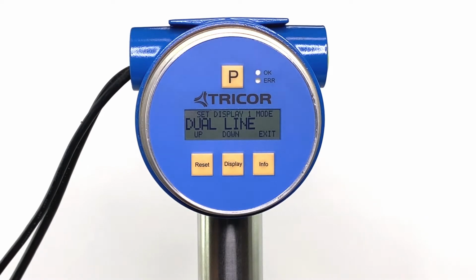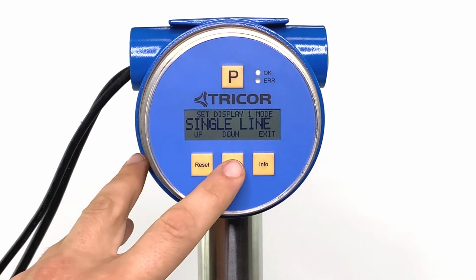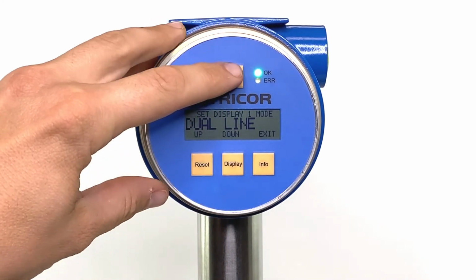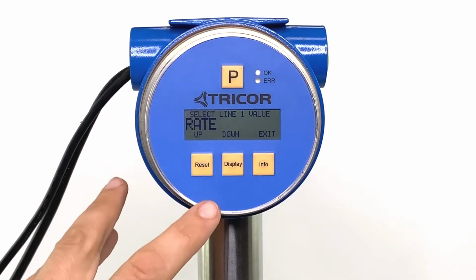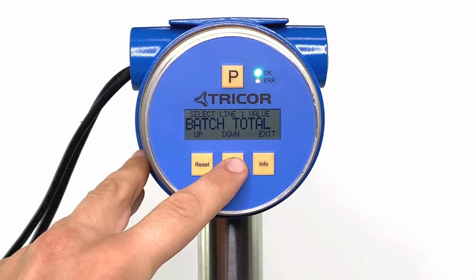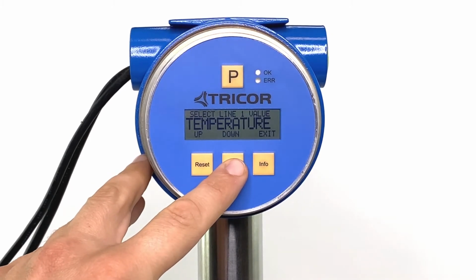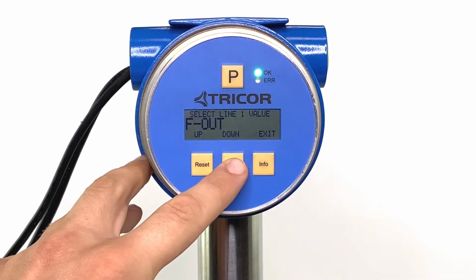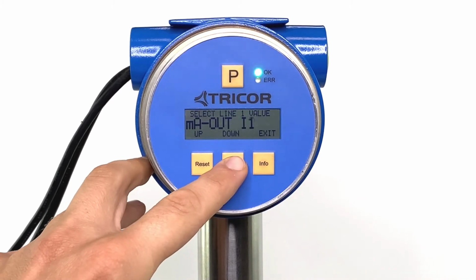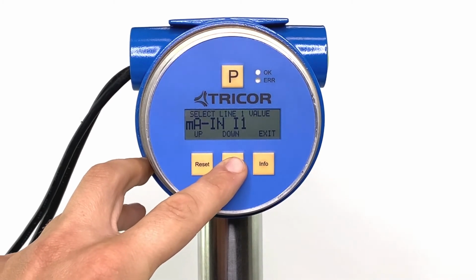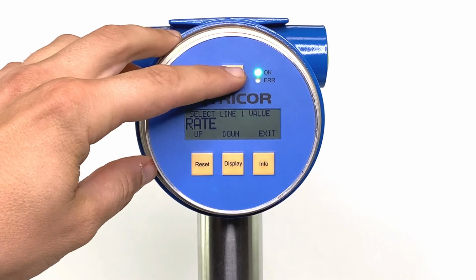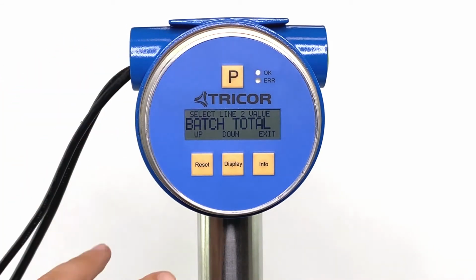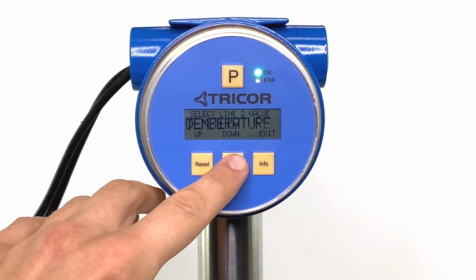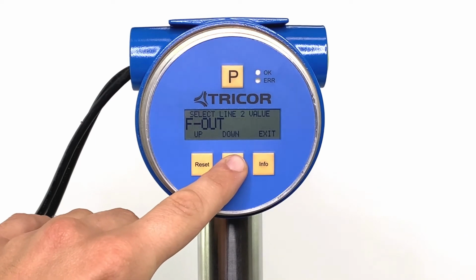You can then cycle between either a dual line display or single line display. Your first option will be for the top line. You can cycle through your different options for rate, batch total, density, temperature, grand total, frequency out, and milliamp outputs. Press P to enter your selection. You can then enter your value for line 2, once again pressing P to enter.